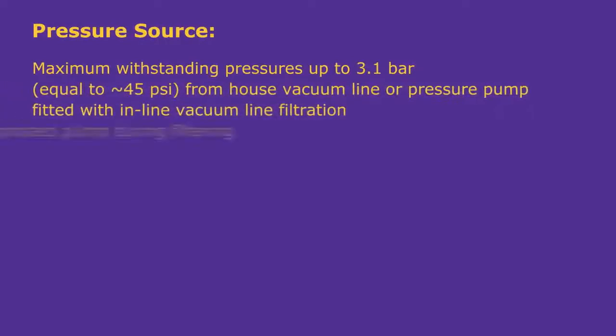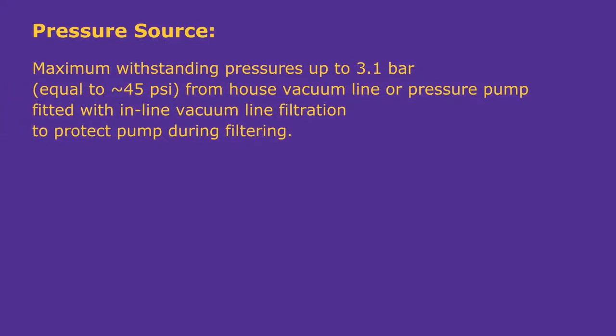Pressure source. Maximum withstanding pressure up to 3.1 bar from house vacuum line or pressure pump fitted with inline vacuum line filtration to protect pump during filtering.